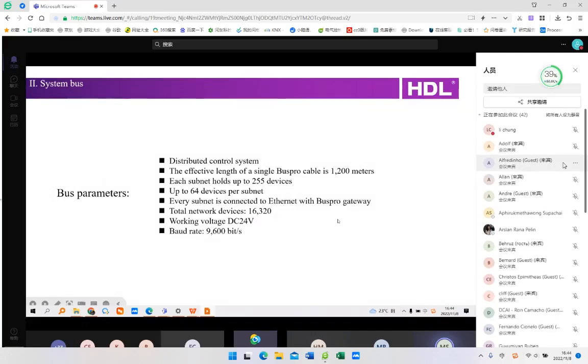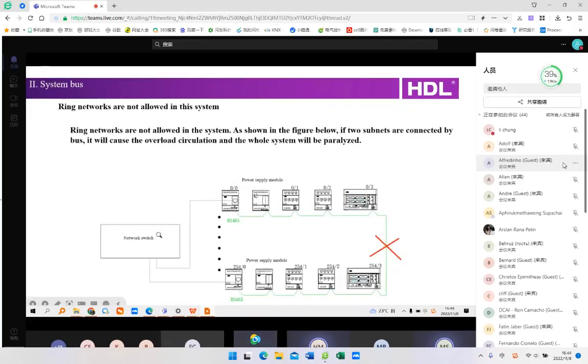So let me make a conclusion. So we have a distributed control system, and most importantly, the effective length of a single Buspro cable is 1,200 meters. That's to say, a subnet can hold as much as 64 devices, but the cable shall not exceed 1,200 meters. If the length exceeds 1,200 meters, please make another subnet and add another gateway. Otherwise, the communication may not be good.